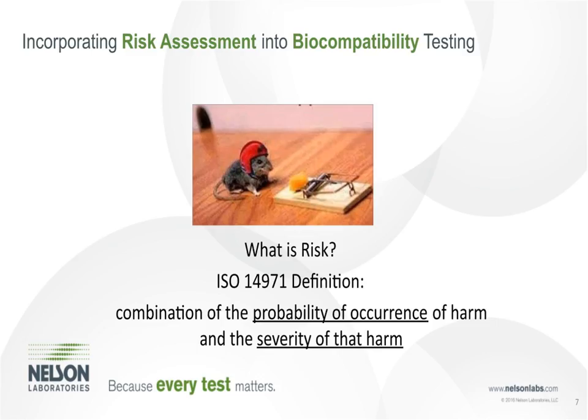When we do that, it's a little bit different from some of the other evaluations in 14971, but the spirit of it is the same. Our probability of occurrence goes into materials and processing and how it's used, and then that goes into an evaluation of the severity and impact of that device. That's why I love this picture. I got this from a friend of mine, Dr.